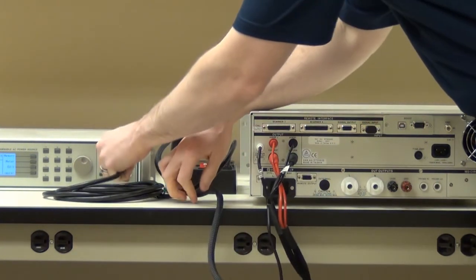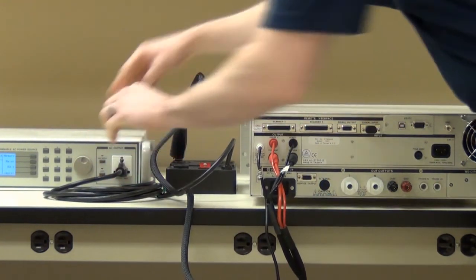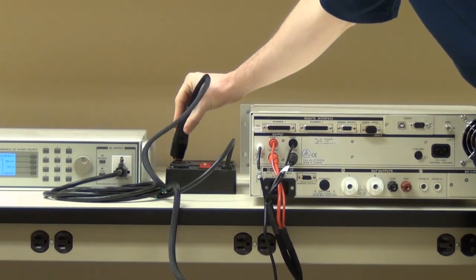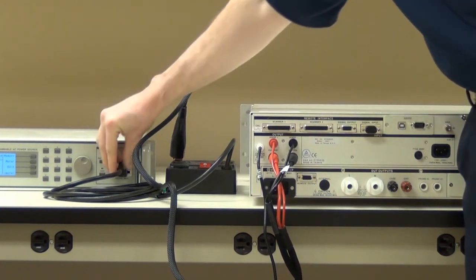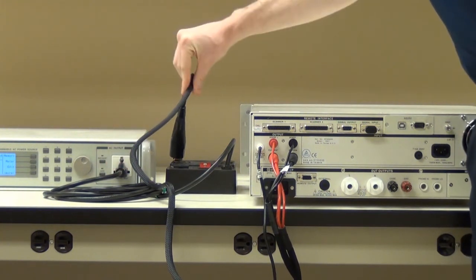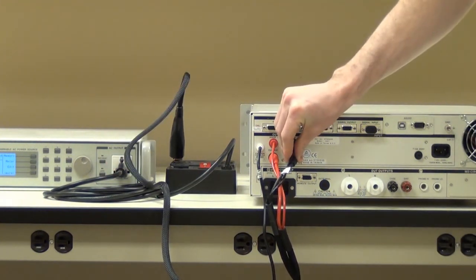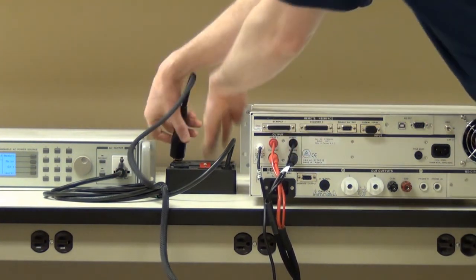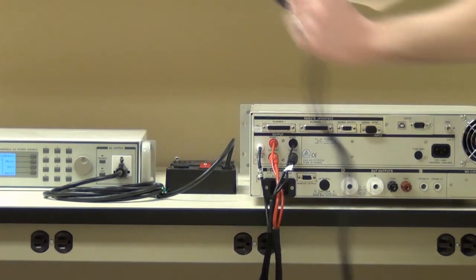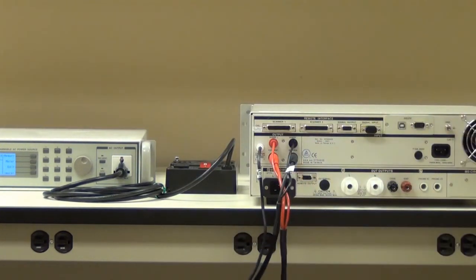and then went on to plug it into the power supply, but left the return lead on, there's the possibility that if something goes wrong during the run test, current could make its way back to the return and damage the instrument. Always remove all leads from the Omnia before moving on to another test station.